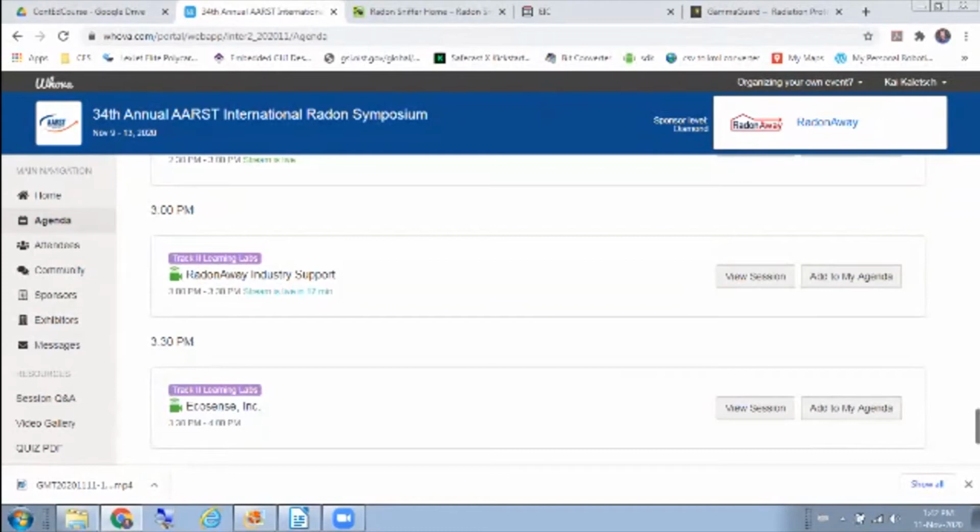Mitigators will have a bunch of holes drilled in the floor, and they will measure one hole for 90 seconds. That allows the sniffer to stabilize and then go straight to the other hole without any recovery time. Would the filter also minimize or eliminate the thoron if it's there as a confounding agent?